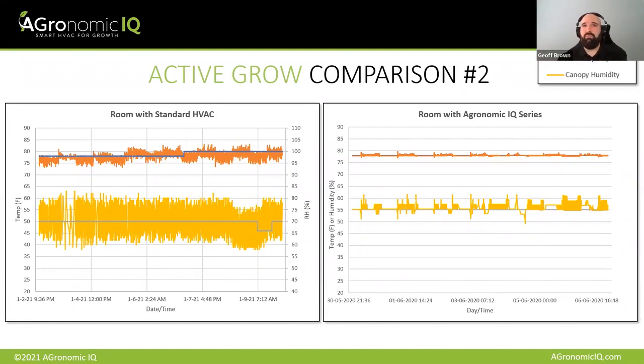Here's another example of a similar room with much more tightly controlled conditions. And again, you can see in this case, there's a 20% relative humidity swing in that room on the left. And we're sub 10% in the room controlled by Ag IQ. So we're controlling it in gross numbers about 50% tighter, although you can obviously see that it's a much more stable environment as well.